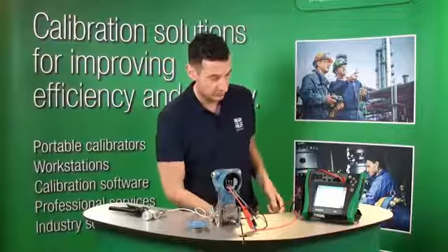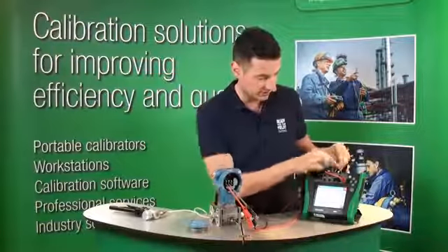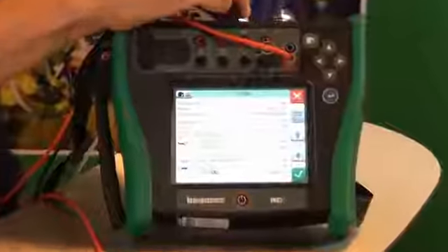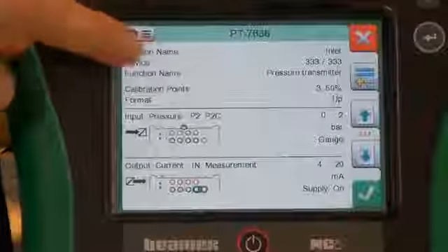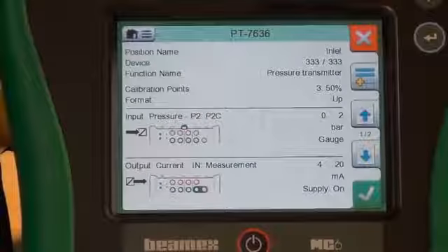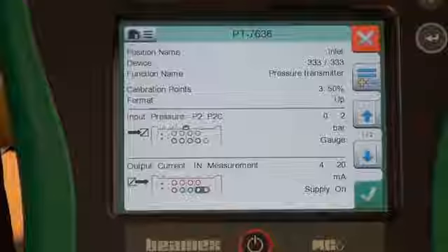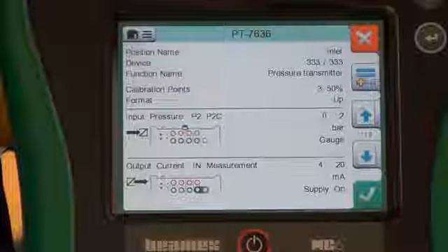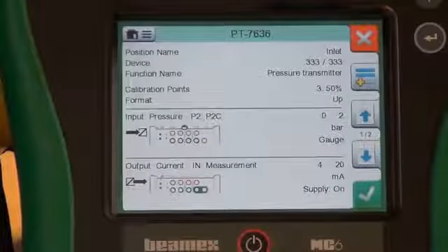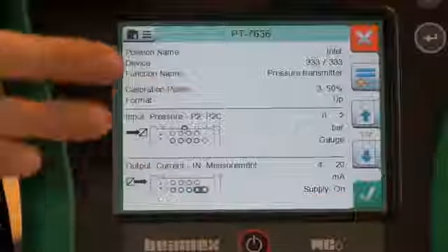We're just going to connect it as shown in the picture there, and also connect the pressure internal modules here, finger tight — no need to use any tools. You can see it's 0 to 2 bar, so this is the range we're going to calibrate this transmitter on, with 3 points: 0, 50 and 100%. So this is what we're going to do with this transmitter.